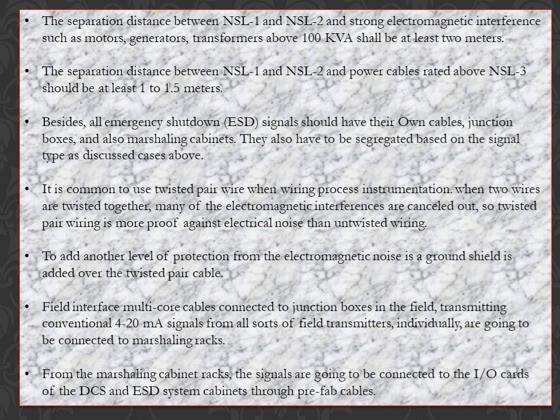It is common to use twisted pair wire when wiring process instrumentation. When two wires are twisted together, much of the electromagnetic interference is cancelled out, so twisted pair wiring is more resistant to electrical noise than untwisted wiring. To add another level of protection from electromagnetic noise, a ground shield is added over the twisted pair cable.